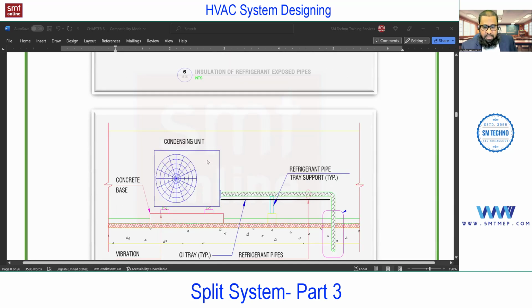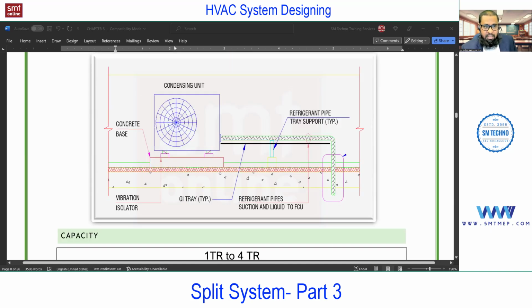Next, apart from this, you see, this is the base for the outdoor unit. You must construct this concrete base, and before connecting, we require these isolators, nothing but rubber pads, to reduce the vibration from the unit to this concrete base.